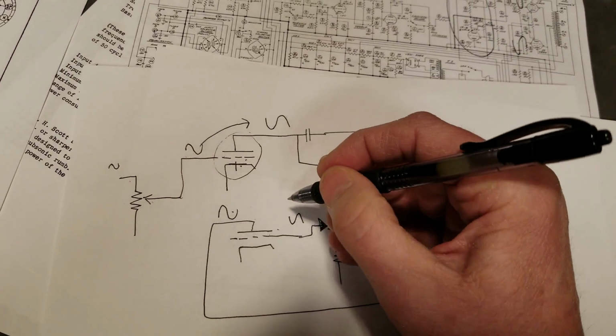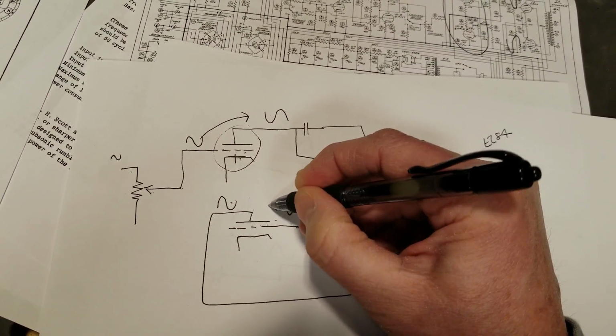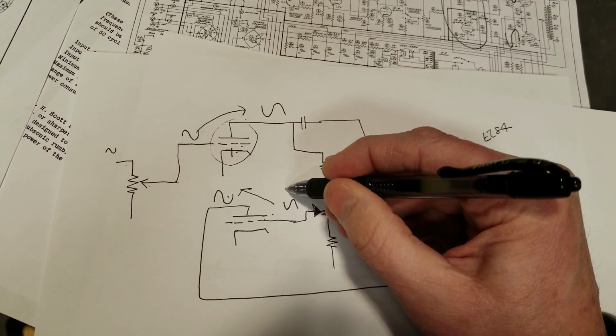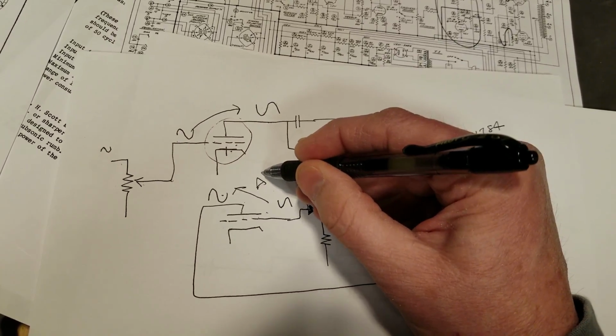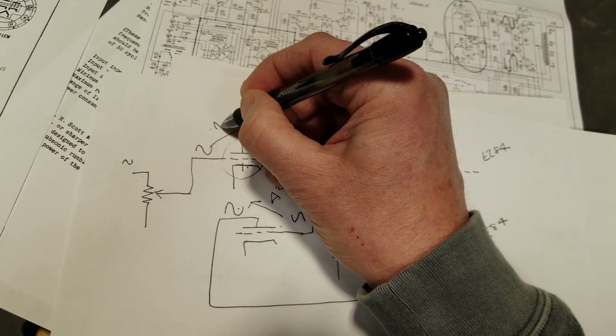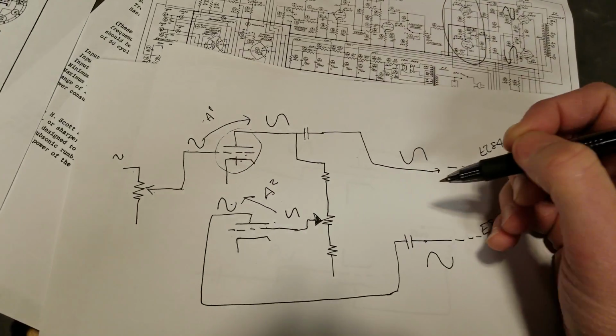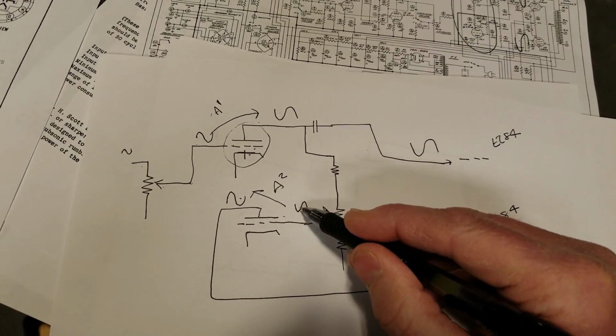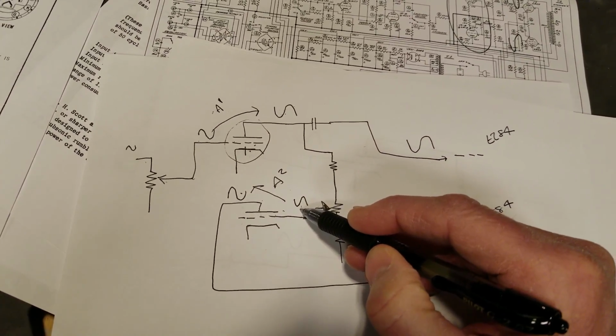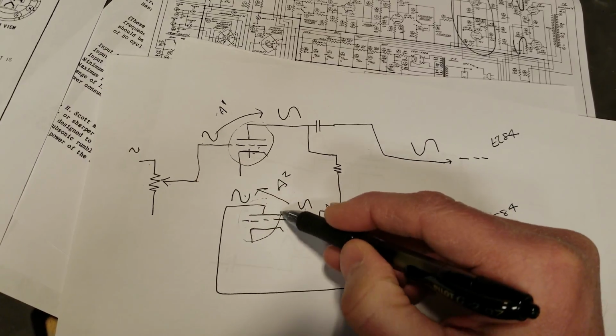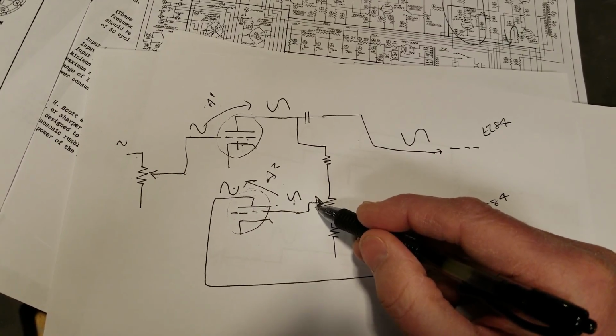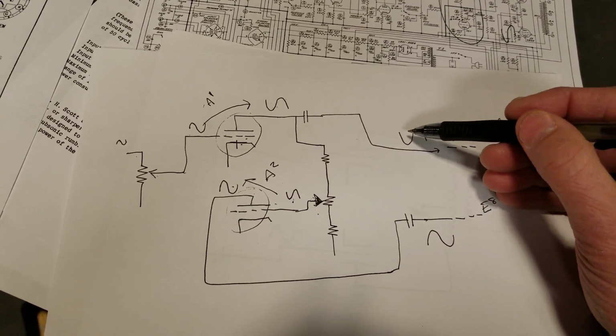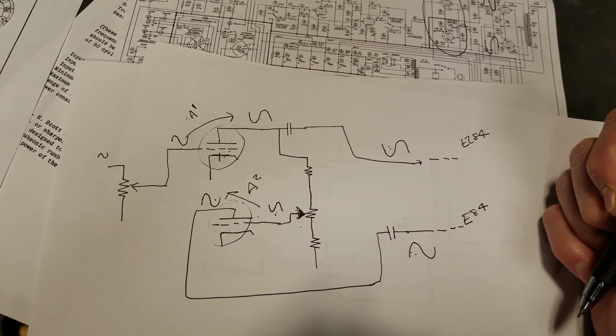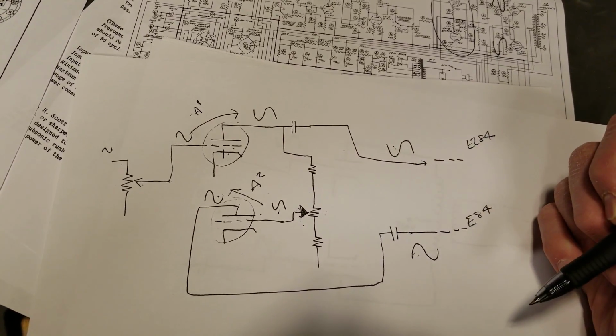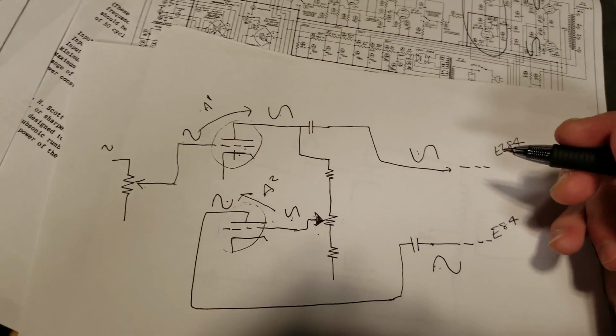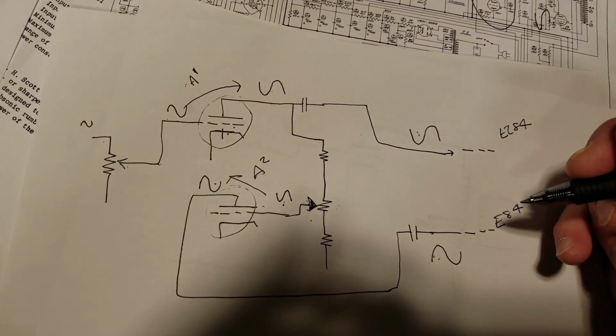Now, the problem is this tube right here is going to amplify an already amplified signal. I'm going to call that A2 and A1 as an amplification factor. So we need to actually reduce this signal a little bit to compensate for the fact that this tube is going to do some amplifying. So we have a potentiometer right here to offset that or adjust that so that these two signals become equal in amplitude. That's called our AC balance. It's actually an adjustment that has to be made to the amplifier on the bench by a technician.